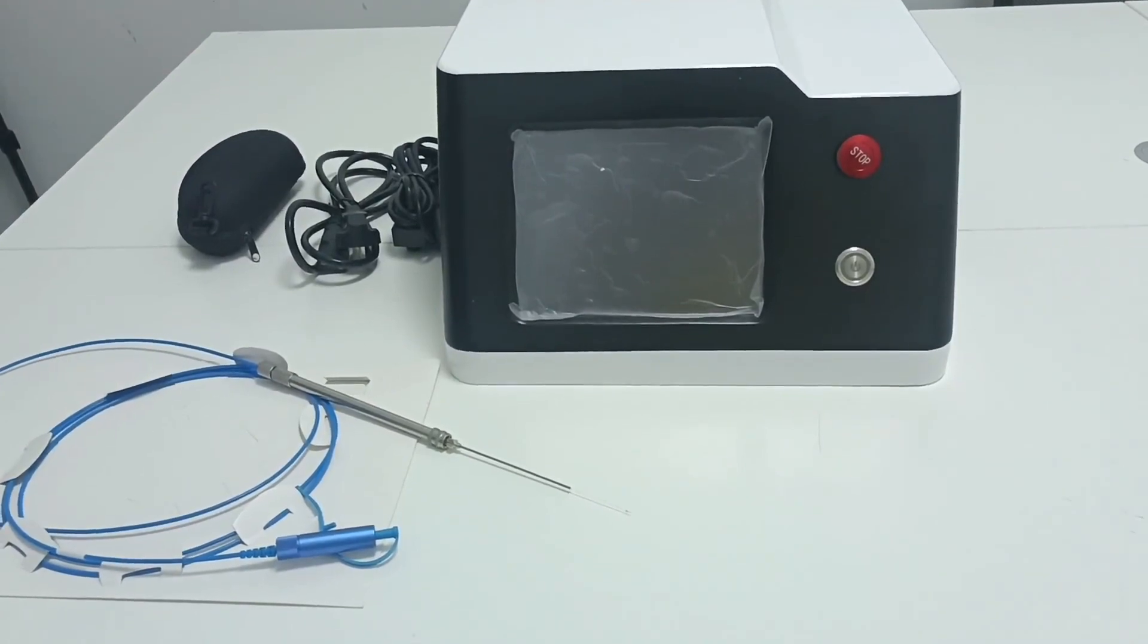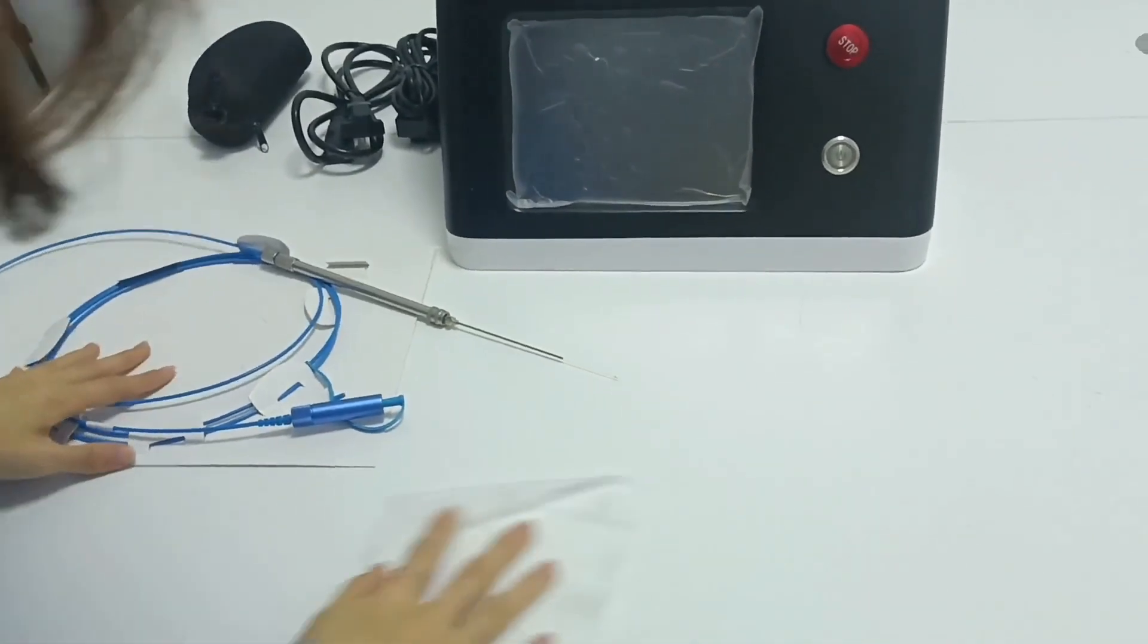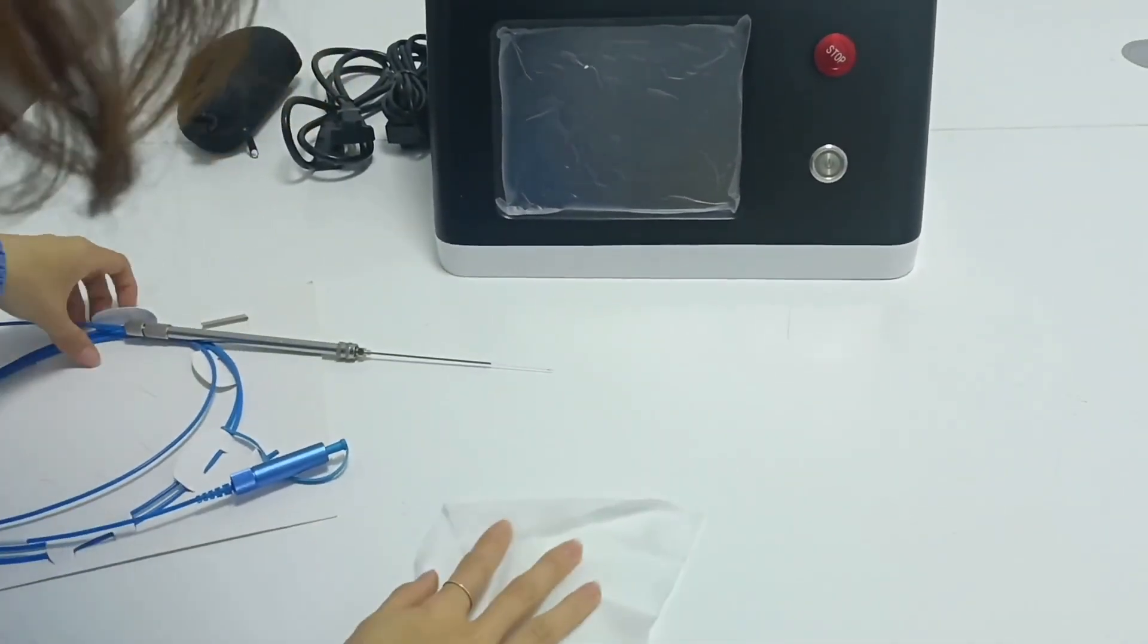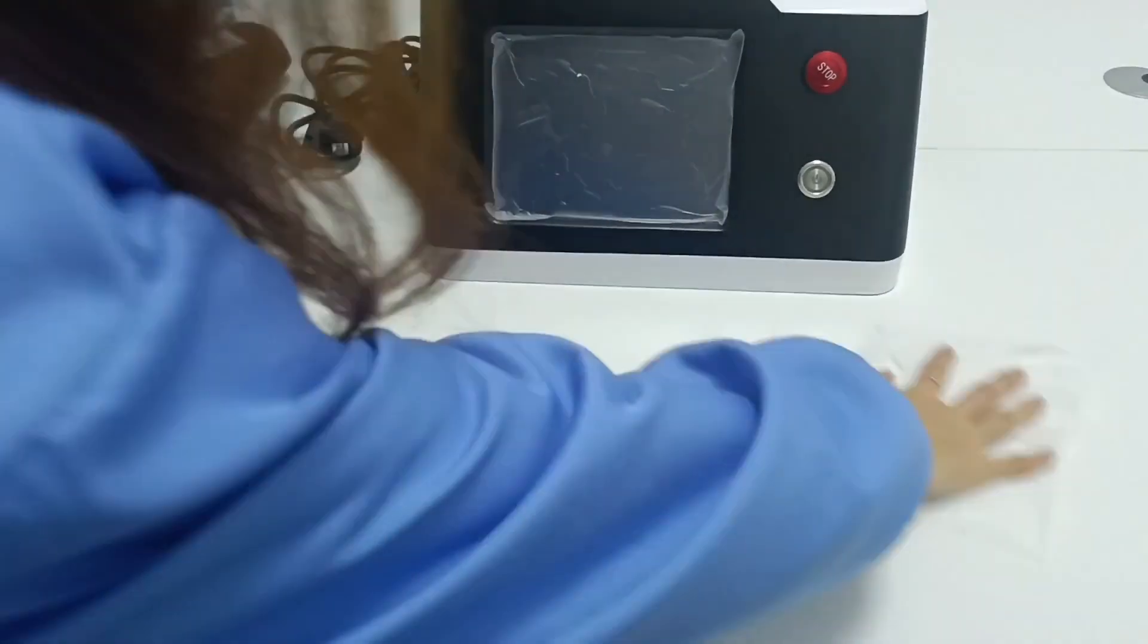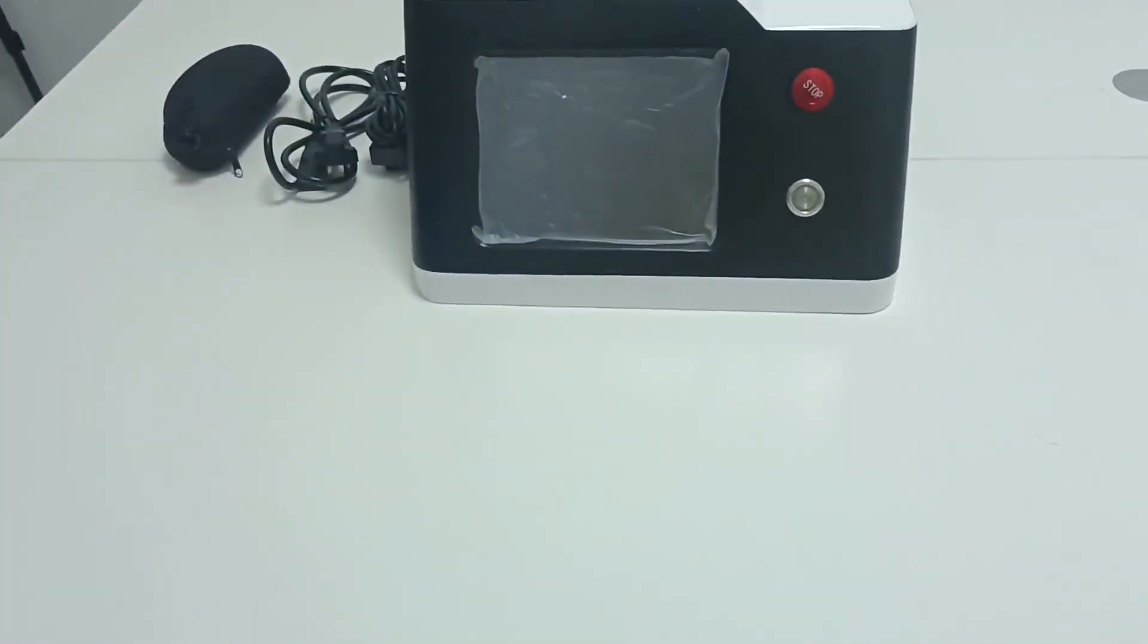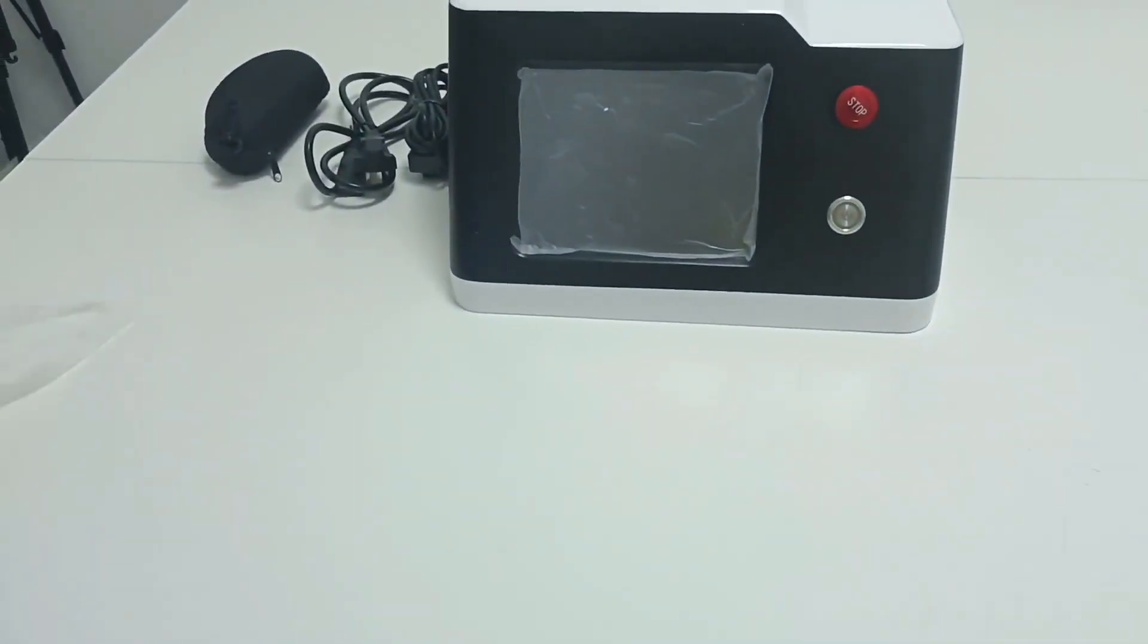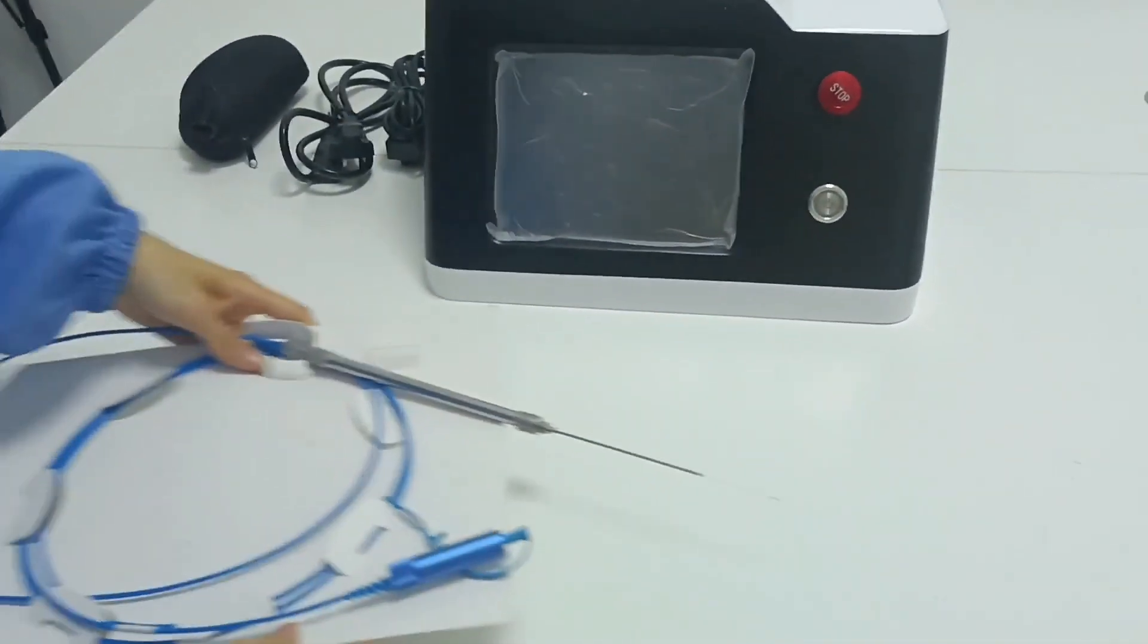2. When replacing the surgical optical fiber, make sure that the surrounding environment is clean and an absolutely dust-free environment as far as possible. Wash and dry your hands and quickly replace the spare.